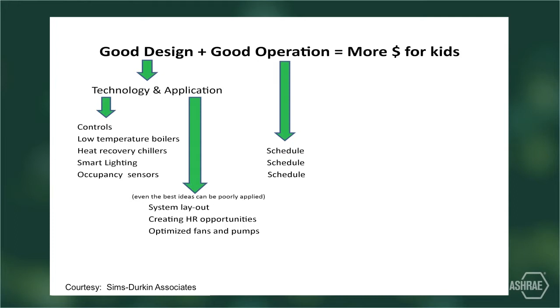Good operation means that the temperature control contractor, the commissioning authority, and the building operators understand and can execute our concepts and possibly improve on them. And just like in real estate, where the three most important factors are location, location, and location, the important factors in efficient operation are schedule, schedule, and schedule. The closer we can match operation to occupancy, the more efficient we'll be.